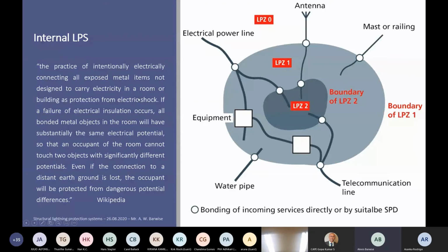The practice of intentionally electrically connecting all exposed metals, right? Not designed to carry electricity in a room or in a building, right? As protection from electric shock. If a failure of electrical insulation occurs, all bonded metal objects in the room will have substantially the same electrical potential. So it doesn't matter if it goes high up even into the kilo or megavolts, they will all have the same because they're all connected together intentionally. So that an occupant of the room cannot touch two objects with significantly different potentials. So we are avoiding shock. Even if the connection to a distant earth ground is lost, the occupant will be protected from dangerous potential differences.